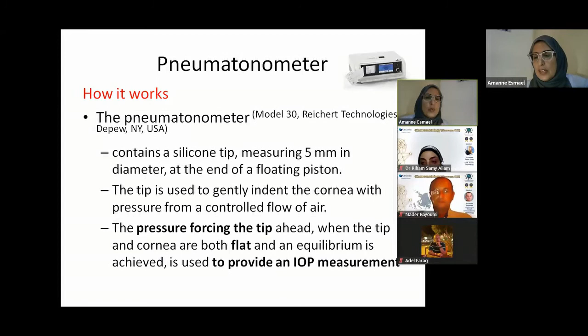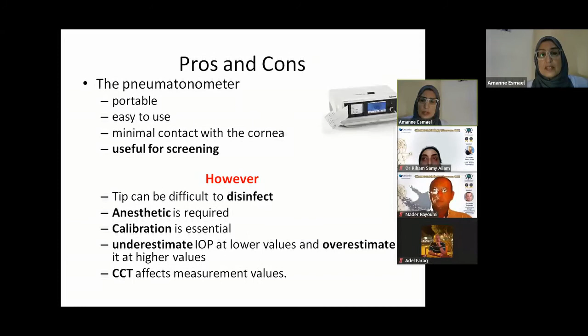Again, it's a portable device, easy to use, with minimal contact to the cornea surface, which makes it useful for screening. However, it's quite difficult to disinfect its tip. It still requires a topical anesthetic. Calibration is essential, and it might underestimate or overestimate intraocular pressures. By most studies, it underestimates at the lower values and overestimates at the higher values. And again, central corneal thickness affects its reading.